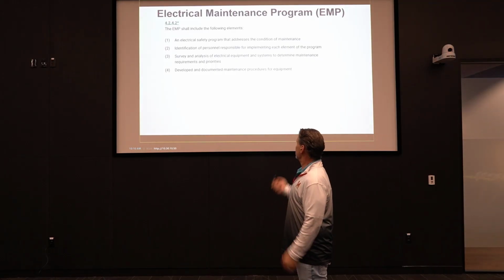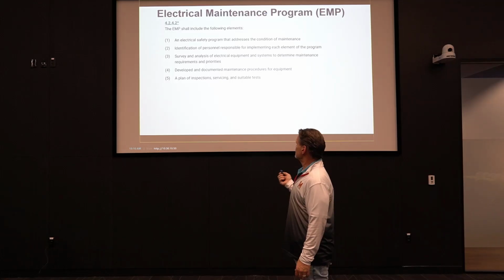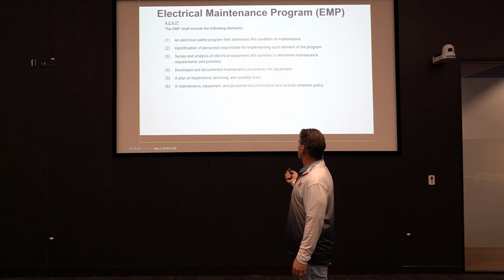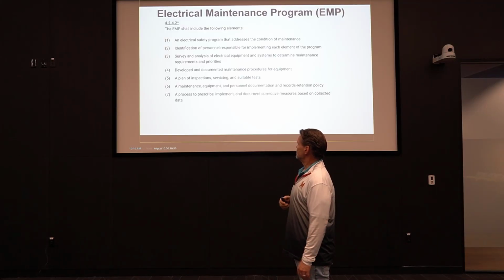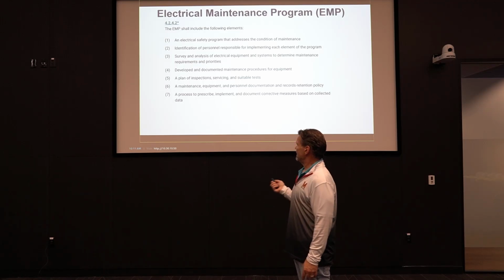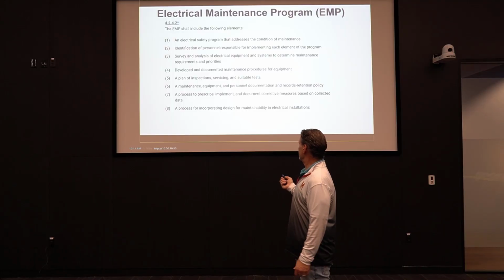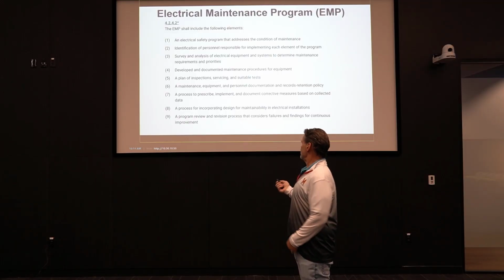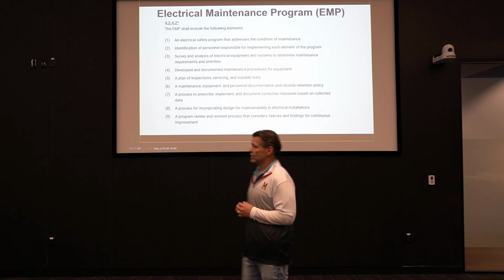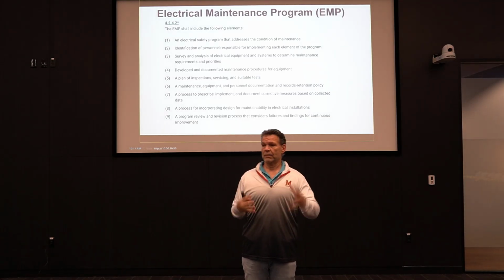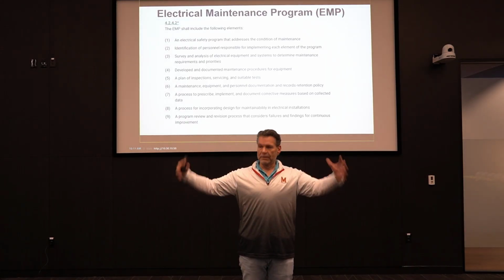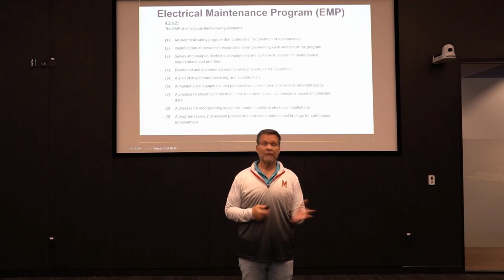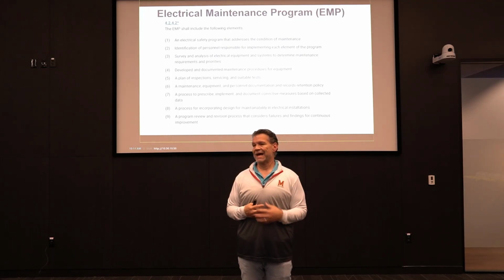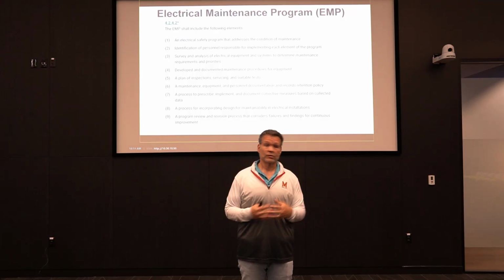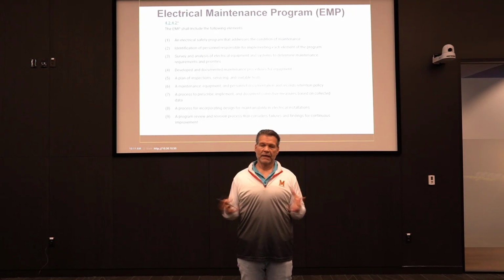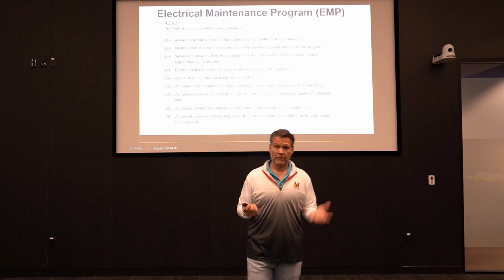Develop and document and maintain procedures for the equipment, plan of inspection, servicing, and suitable testing, maintenance equipment and personnel, documentation and record retention policy, and a process to prescribe, implement, and document corrective measures based on that data, and incorporating design for maintainability in electrical installations, and a program review and revision process that considers failures and findings for continuous improvement. So obviously you're always trying to get better, trying to make sure that the equipment is being maintained properly, and then moving forward, everything is going to be on track so that it is as safe as possible, but it's also about reliability, functionality, making sure the equipment is doing what it's supposed to do, so that whatever industry you're in, whatever company they are, they can continue to have that equipment working in a functional environment for their product.